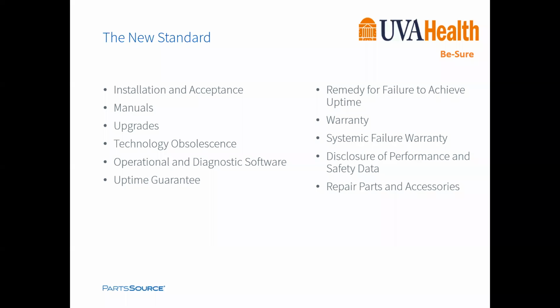We've addressed the old issue of vendors saying they would not give us manuals, including service literature, for free. We take on upgrades in these terms and conditions, and that's not just updates, but upgrades, and I'll work to try and define those. We take on technology obsolescence, or solving for the risk that we're buying technology at the end of its life cycle, and I'm sure that's happened to many of you on the call. Diagnostic software, our uptime guarantee, what are the remedies for failure to achieve that uptime?